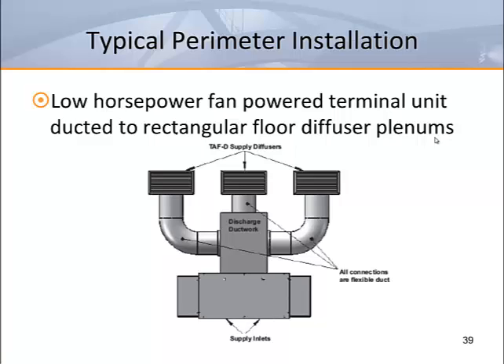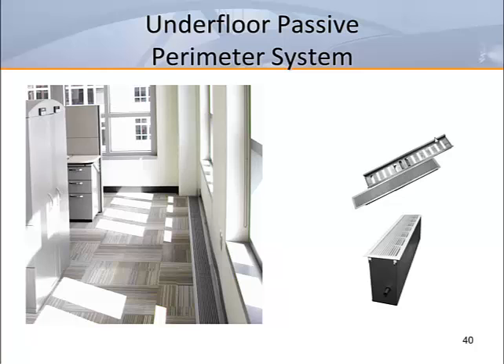For underfloor air distribution applications, fan terminal units are typically equipped with ECM motors for maximum energy efficiency. ECM motors can be controlled by the building management system to vary the amount of air delivered to match the load in the space. These fan-powered terminal units may also be equipped with hot water coils or electric heating coils. This is an underfloor passive perimeter system. This perimeter underfloor system operates to match the varying load conditions without employing the use of a fan-powered terminal.